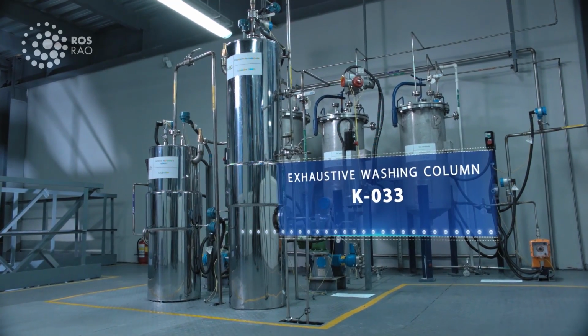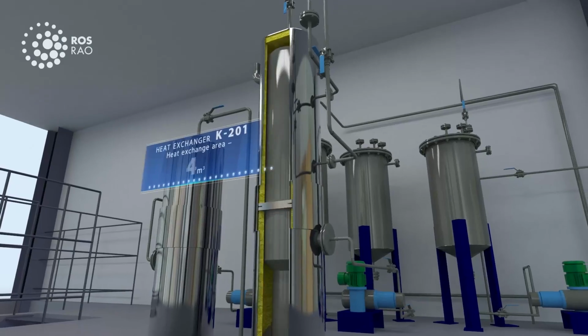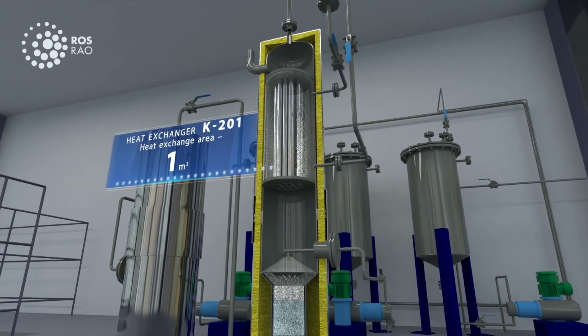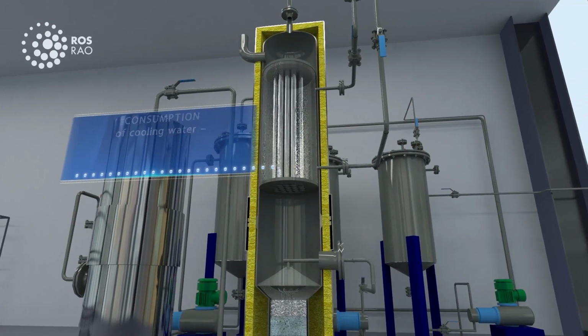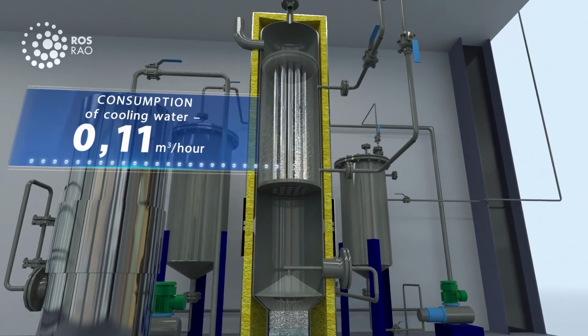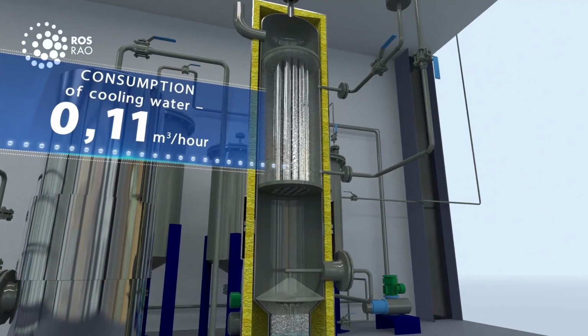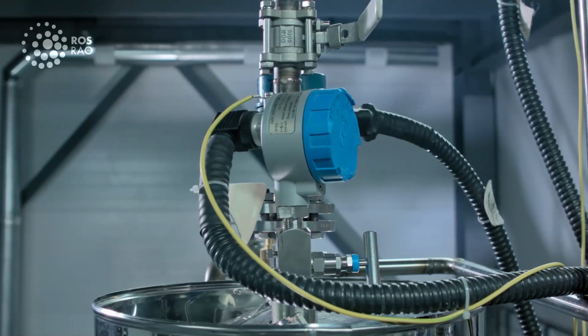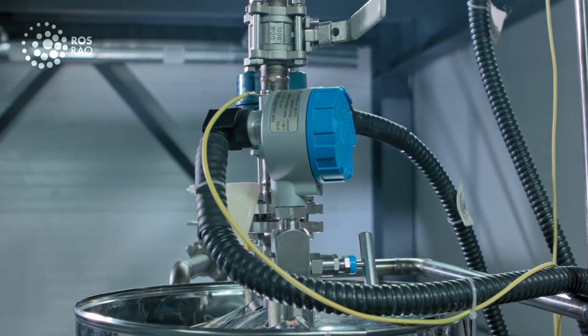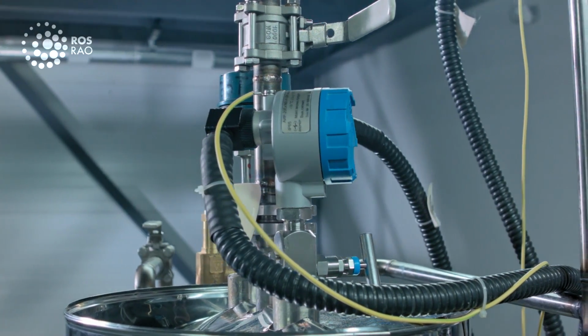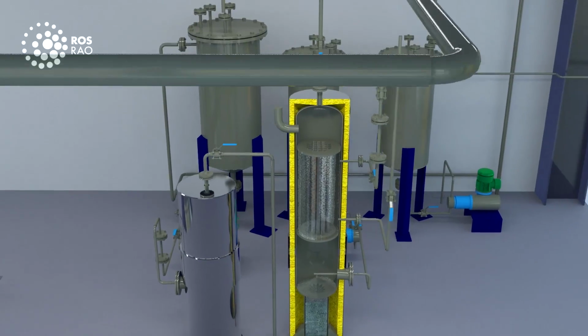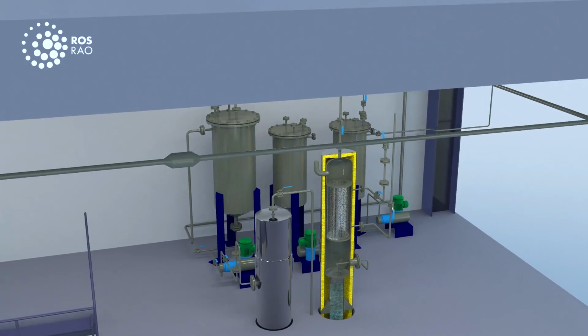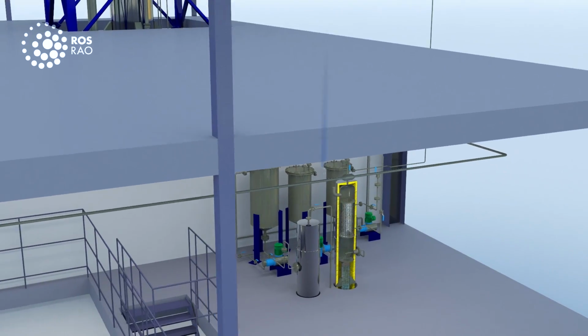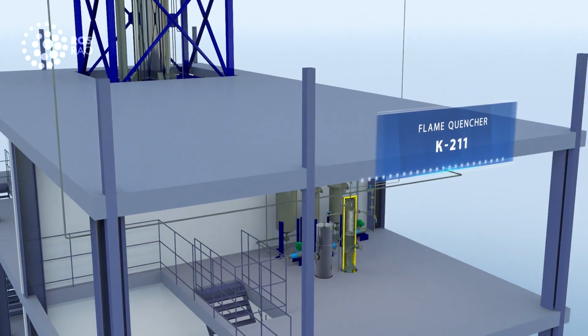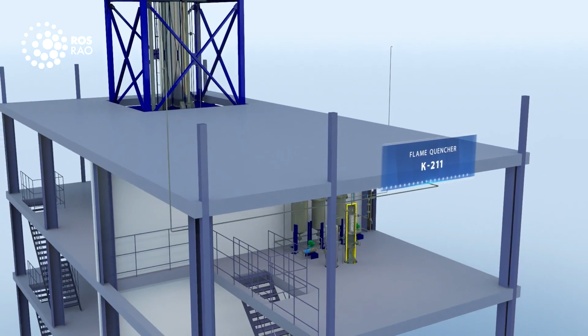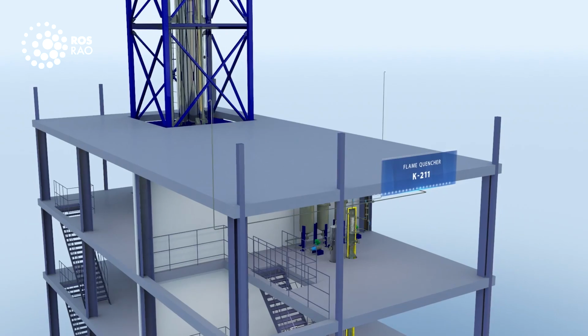The hydrogen from wash column K33 arrives at heat exchanger K201 for drying. The condensate from the bottom of heat exchanger K201 is returned to wash column K33. The hydrogen from heat exchanger K201 passes through flame arrestor K211, installed to prevent combustion of the volatile mixture, to gas discharge manifold K231, from which it is discharged to the atmosphere.